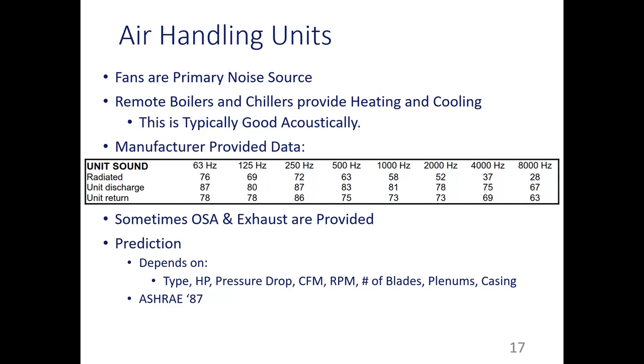Sometimes they bring in outside air, so you're mixing in a certain amount of fresh air. And when it does that, you're exhausting part of it as well. So that's a really basic unit. There are variants of this, like a dedicated outdoor air system or a makeup air unit. But it's just this casing with fans in it and air coming in and out in various configurations. The fans are the primary noise source. There aren't condensing units in it.